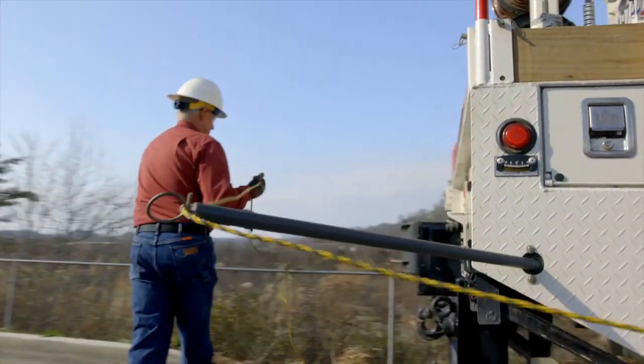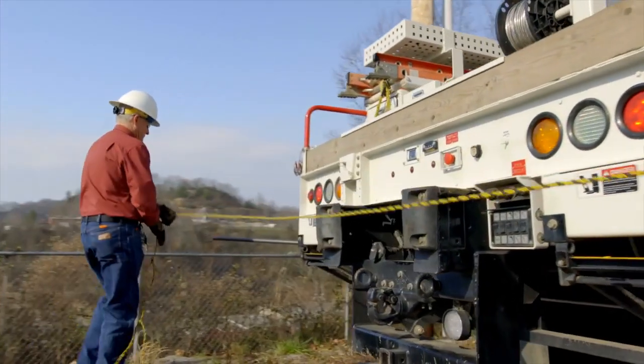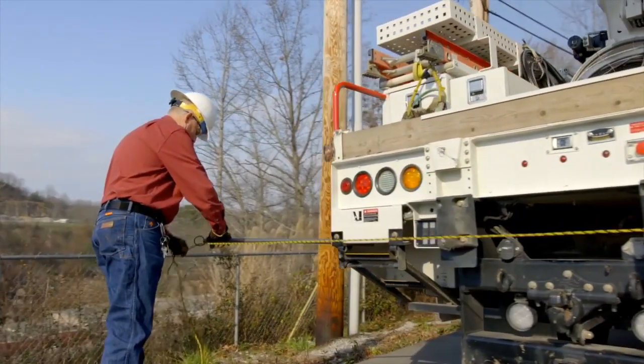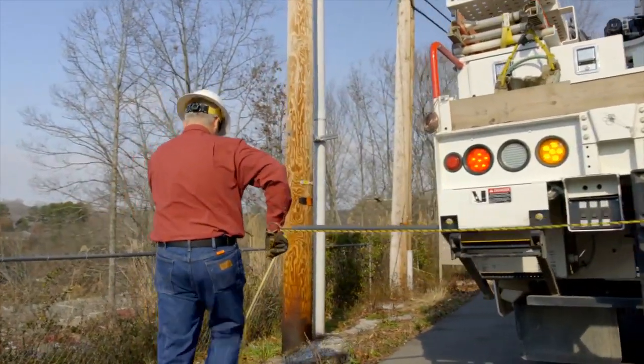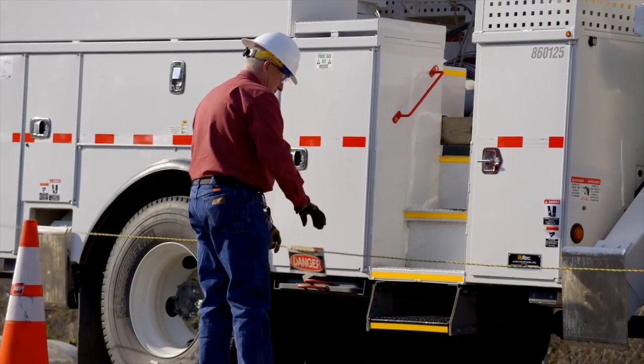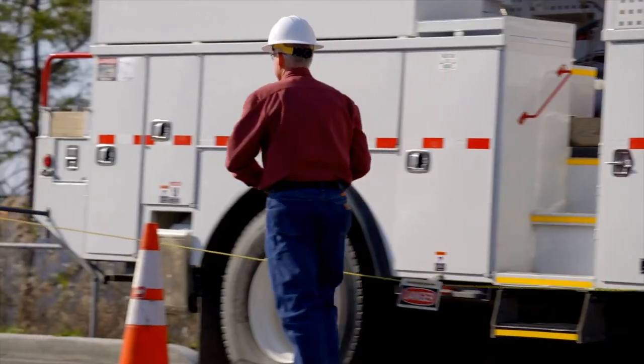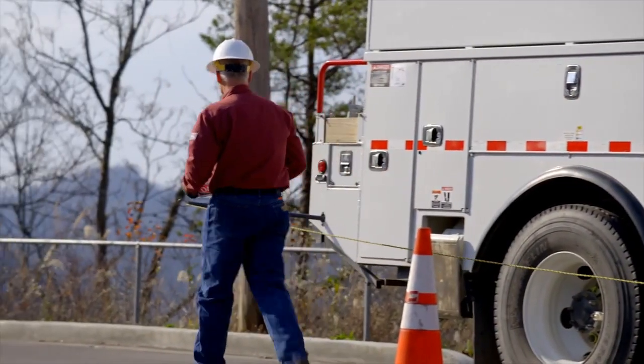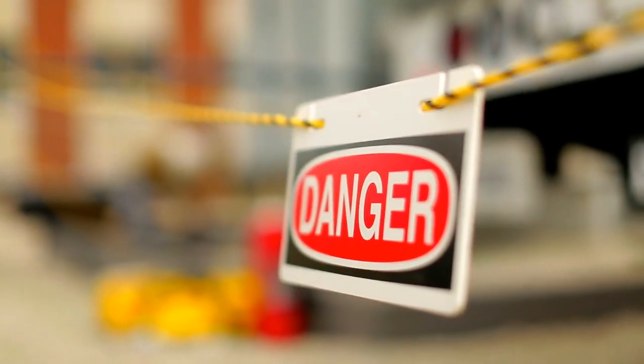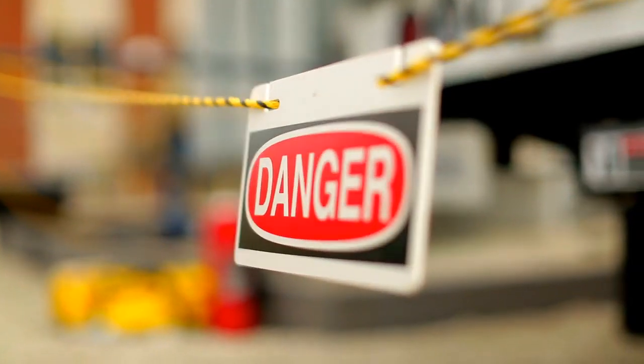After establishing the work zone, set up barricades. If you have temporary ground rods or anchors up, the barricade should be beyond those. Only the qualified observer can let people into barricaded areas. Work aloft has to stop and move away from any energized sources before someone can enter the area.